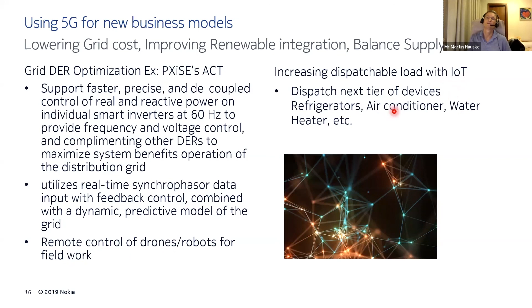Fast forward to the grid of the future. Traditionally the SCADA system has several thousand points. Now with devices like smart meters, smart inverters, EV charging, all those devices at the pole, as well as DG, that leads us to a utility with 4 million customers having more than 12 million devices in the field. This is already a scale that traditional SCADA and ADMS cannot handle.